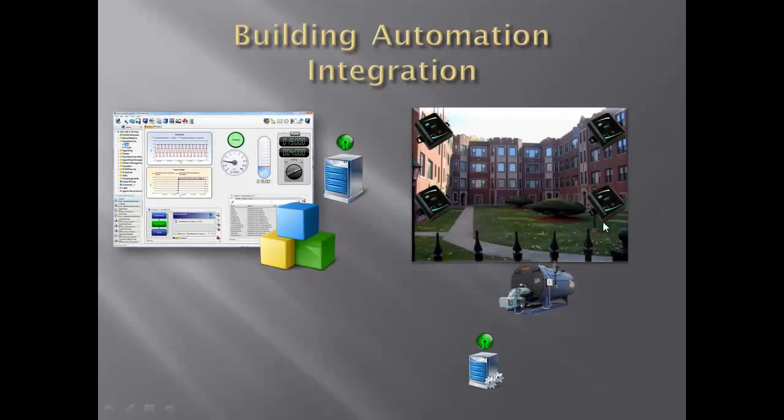And we place some wireless sensors using a technology called Zigbee around the apartment complex in various locations. This is going to feed us wireless data back to this solution engine. And then we also have a wireless connection so that we can turn on or off the valve with an intelligent outlet, you can think of it, and also some temperature sensors on that boiler. So once we have that information, then we take Solution Builder and start configuring the solution engine with the rules, with the interfaces to the hardware that we require, maybe through Zigbee in this scenario, and also through any models that we might be running that are controlling that.